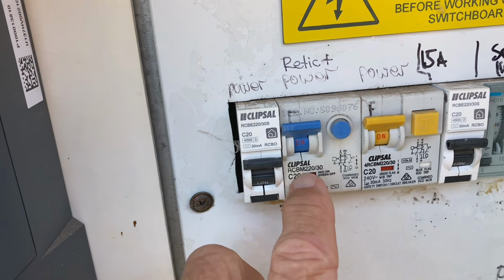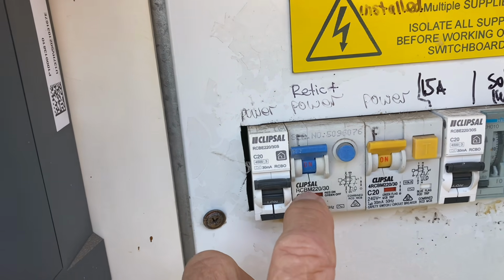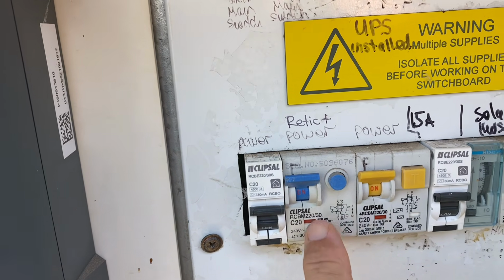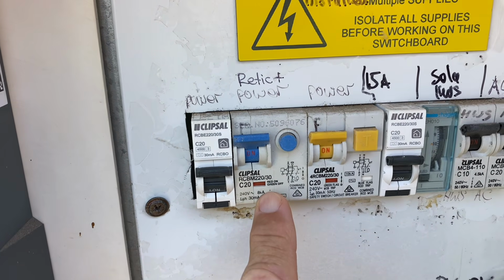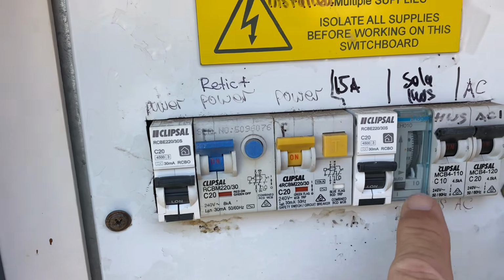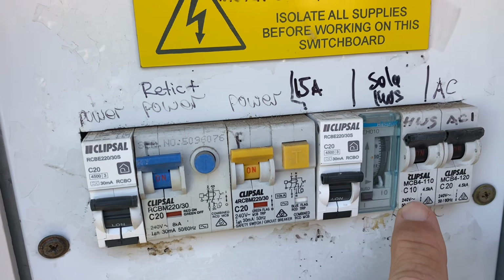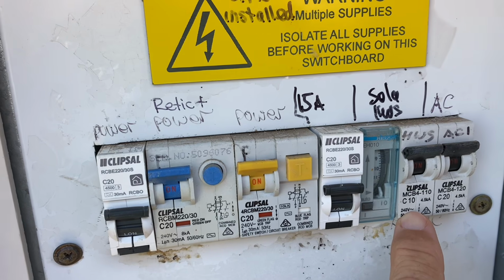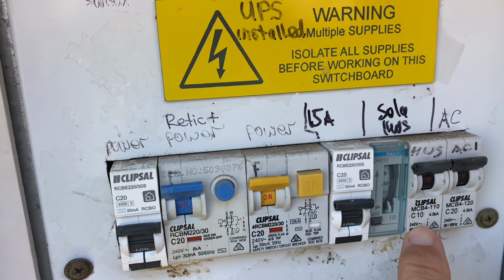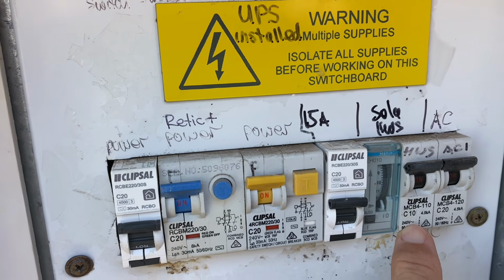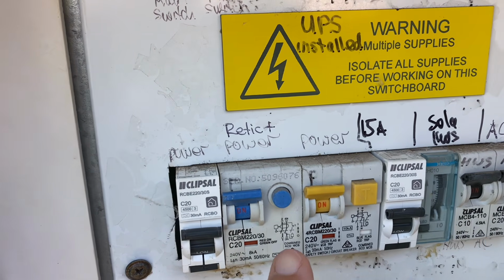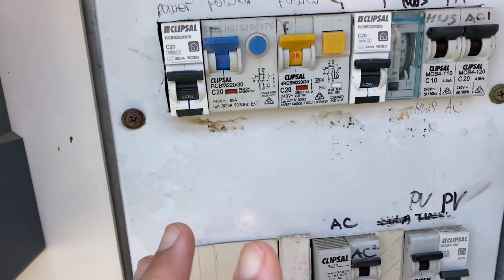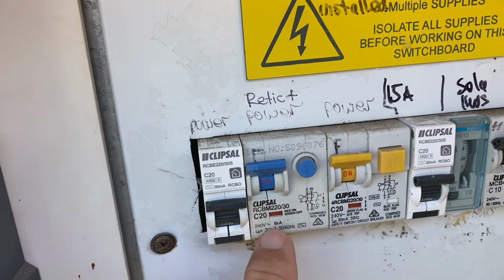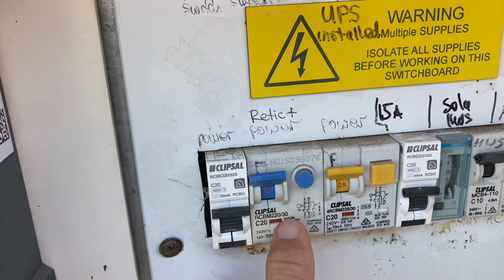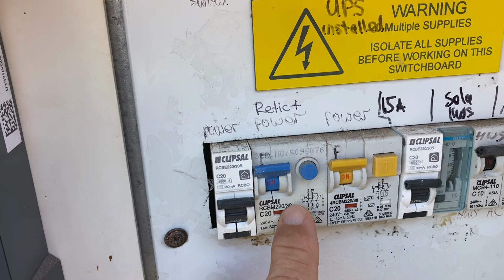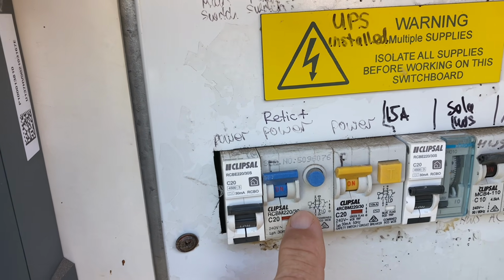So if we have a look at this, this is called an RCBM or an RCBO. This is a combination RCD and a circuit breaker. So this is a regular circuit breaker that protects your house wiring from catching fire due to being overloaded and getting too hot, or from short circuits. An RCD, which I don't have a straight RCD on here, but an RCD just looks basically like this. This is to protect the people in the house from earth faults.